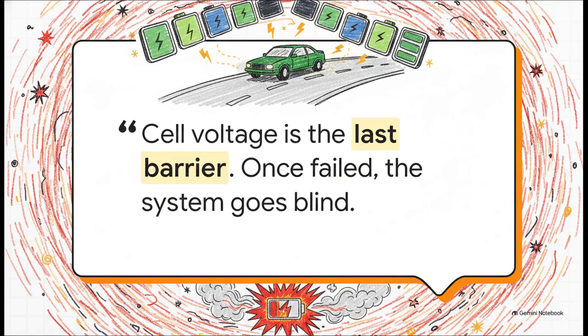Well, that quote really hits the nail on the head. Cell voltage is literally your last safety barrier. If the battery management system, the BMS, loses its voltage sensors, the whole system goes completely blind. Think of it like driving down a highway at night with no headlights. Without accurate cell voltage readings, the system completely loses its ability to stop overcharging or over-discharging. And in a high-voltage lithium-ion battery pack, going blind like that opens the door directly to thermal runaway and a potential fire.